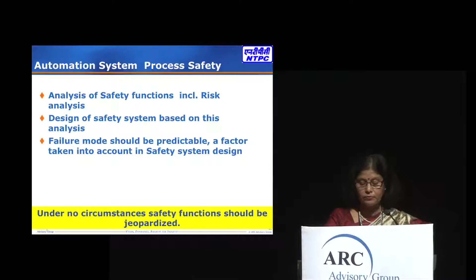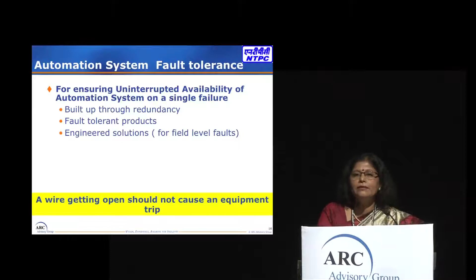Design of the safety system should be based on this analysis. Failure mode should be predictable, a factor taken into account when designing the safety system. Then the system has to be fault tolerant, ensuring uninterruptible availability of the automation system on a single failure—nobody can accept one wire getting open causing equipment to trip. This is just not acceptable. This aspect of engineering is very important, achieved through redundancy, fault-tolerant products, and engineered solutions, especially for field-level faults.